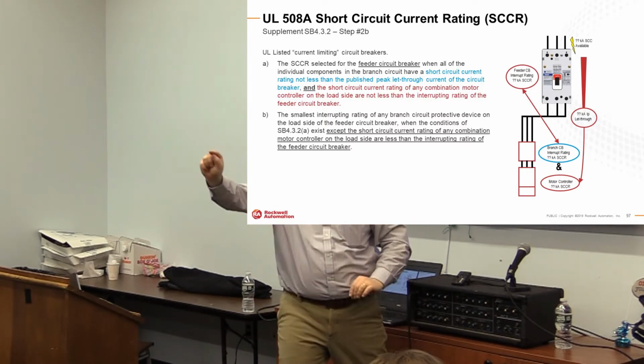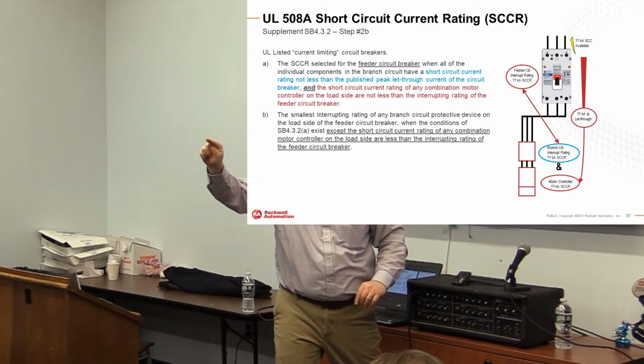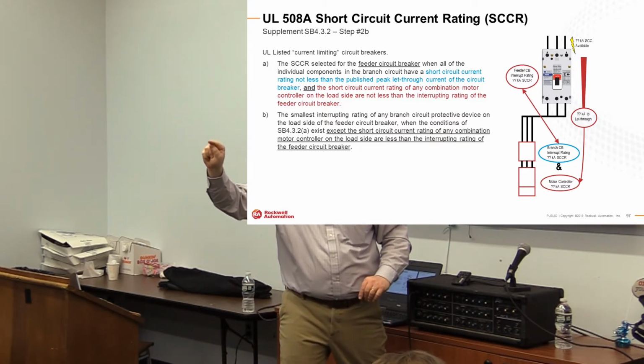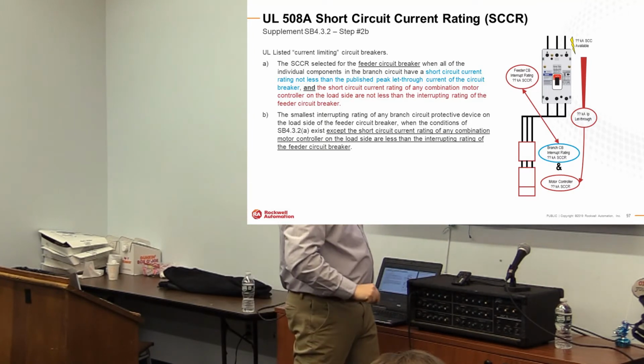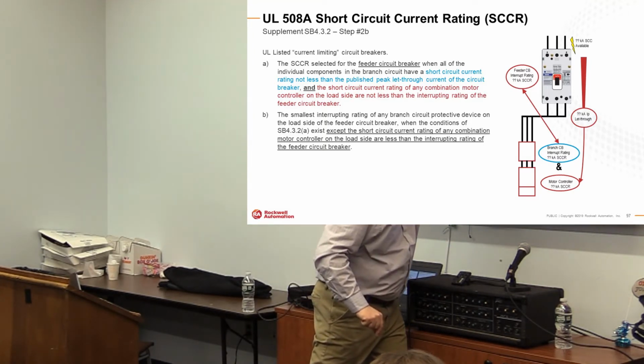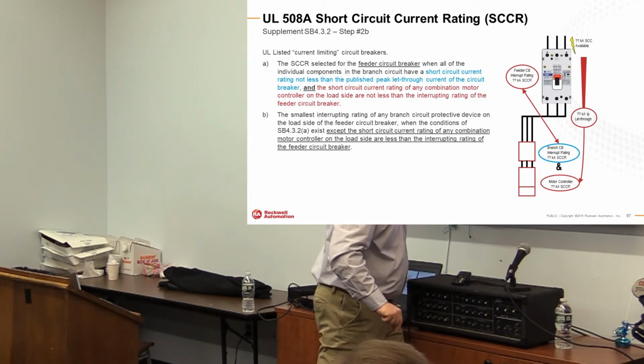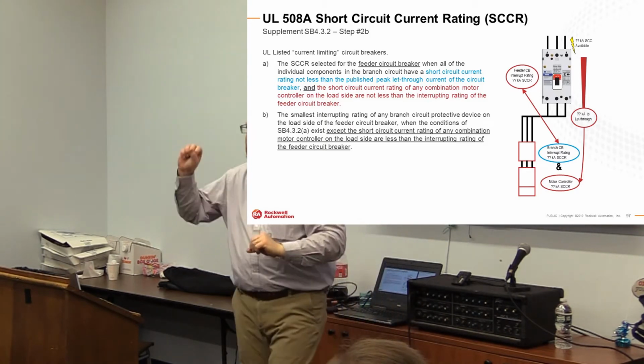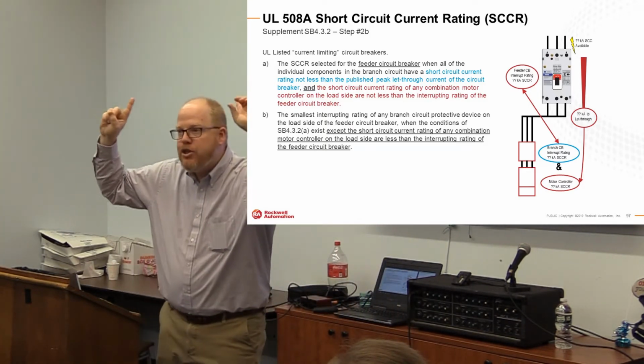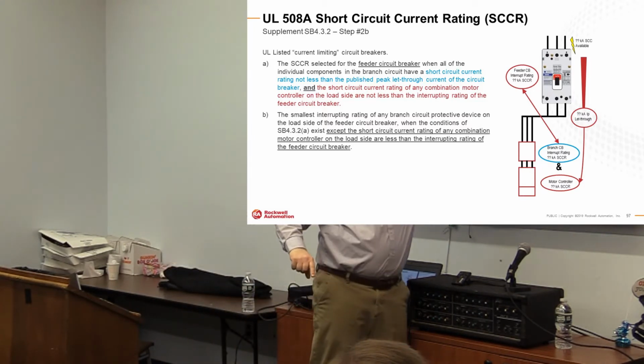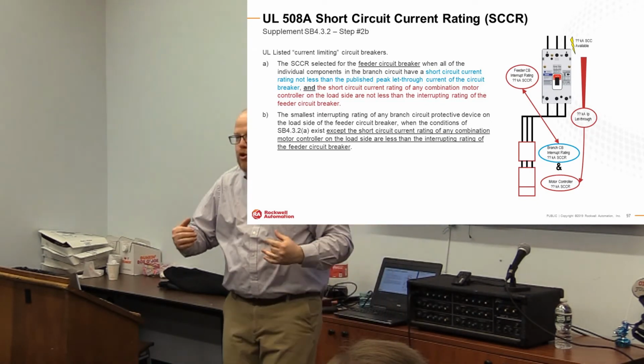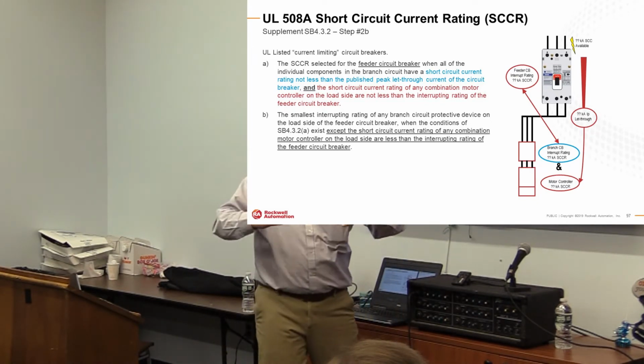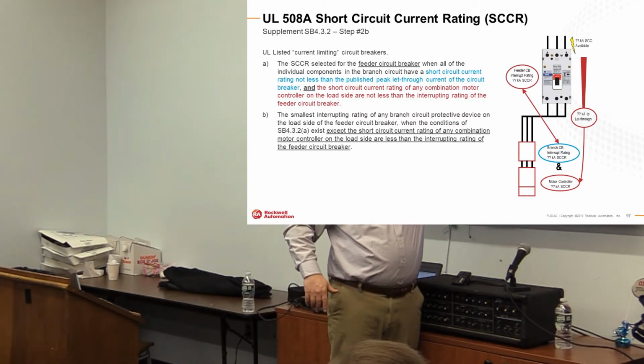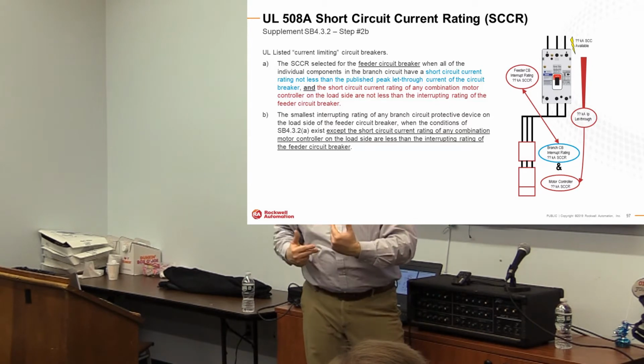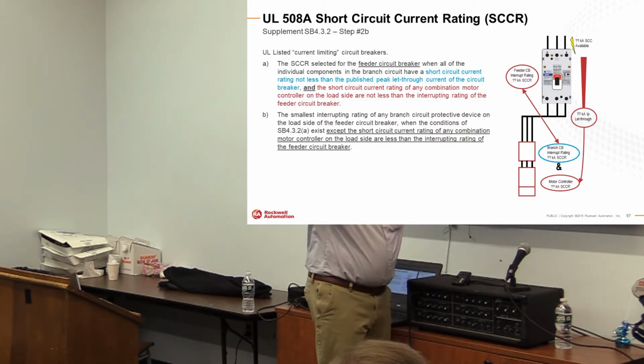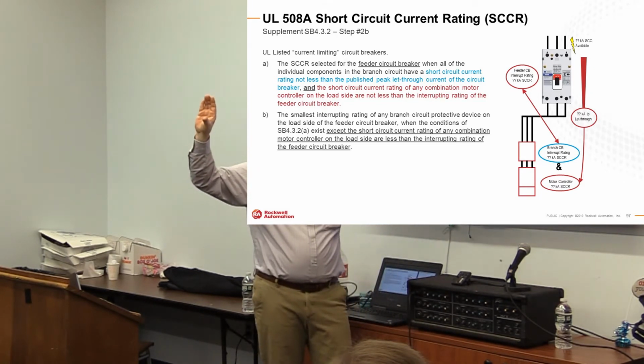And it's not an or, it's an and: the short circuit current rating of any combination motor controller on the load side is not less than the interrupt rating of the feeder breaker. What that is saying is we need to look at the interrupt rating of this breaker, okay? So we have to look at two things: peak let-through, and we have to match the interrupt ratings of the branches to the feeder. Okay, so if you buy a current limited breaker that has an interrupt rating of 65,000 amps, and you want to claim the peak let-through and the current limiting rules that that breaker provides, every one of the branches needs to have a matching interrupt rating.